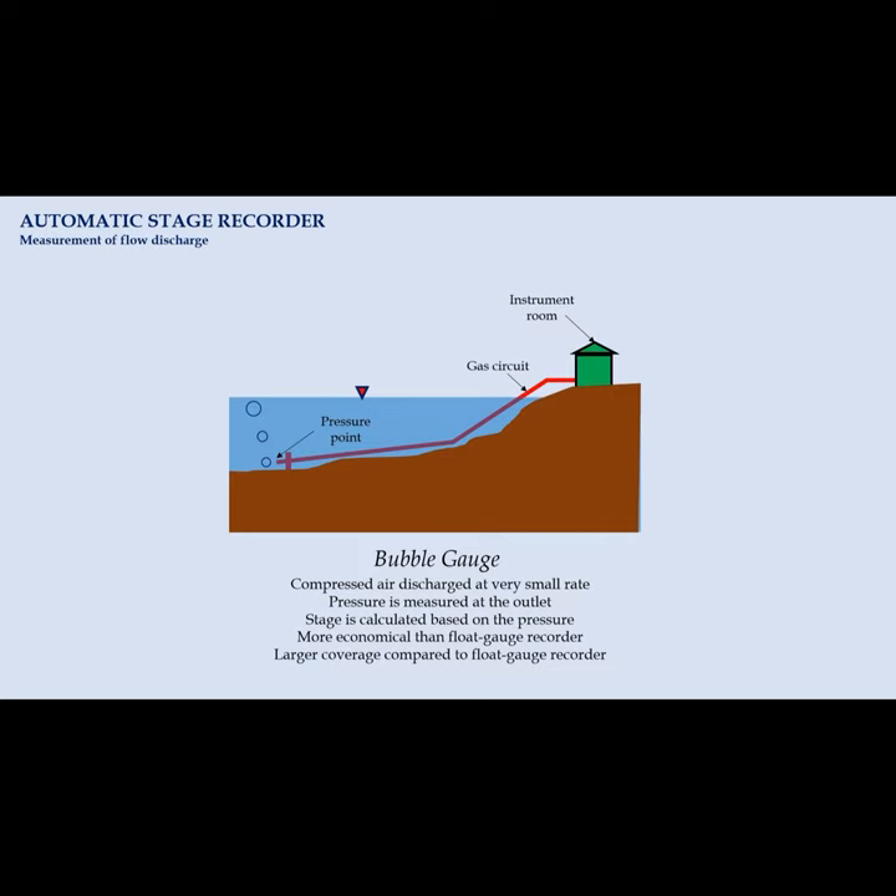A bubble gauge is sometimes preferred over a float gauge recorder for several reasons. The installation of a bubble gauge does not require a stilling well, and thus it is a more economical approach. Moreover, the instrument can work despite having large changes in stage.